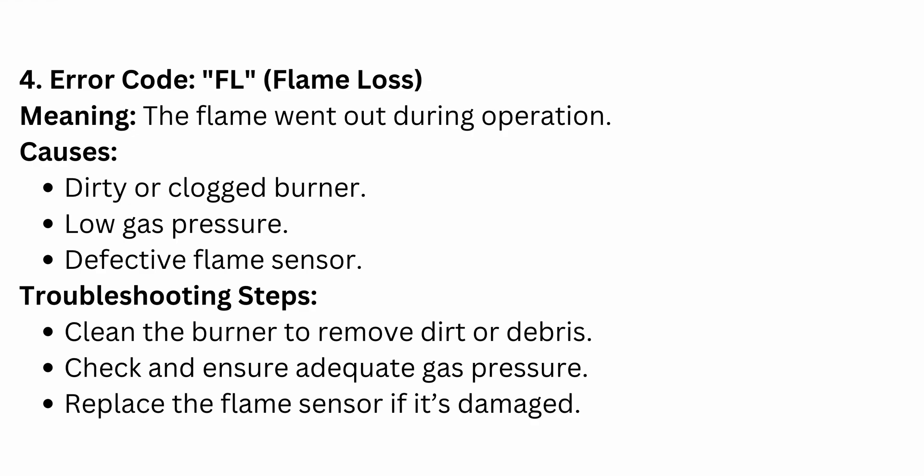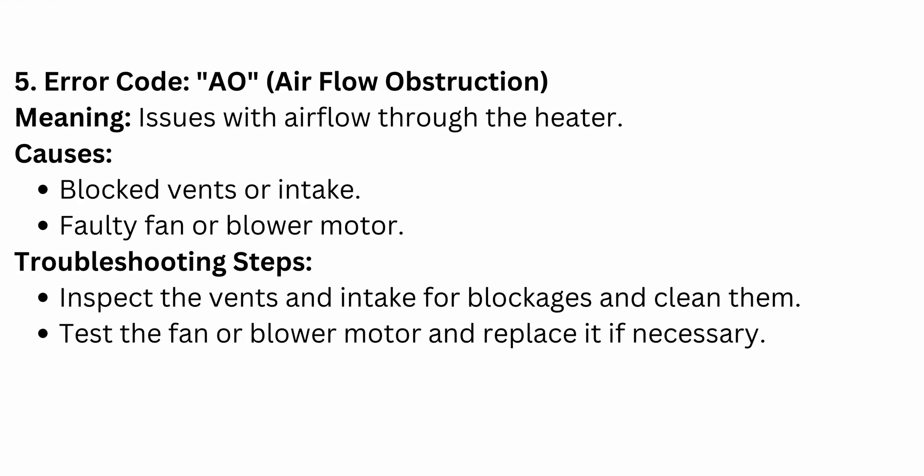Another code is FL, which stands for Flame Loss — the flame went out during operation. Causes can be a dirty or clogged burner, low gas pressure, or a defective flame sensor. The steps to troubleshoot are: clean the burner to remove dirt and debris, check and ensure adequate gas pressure, and replace the flame sensor if it is damaged.